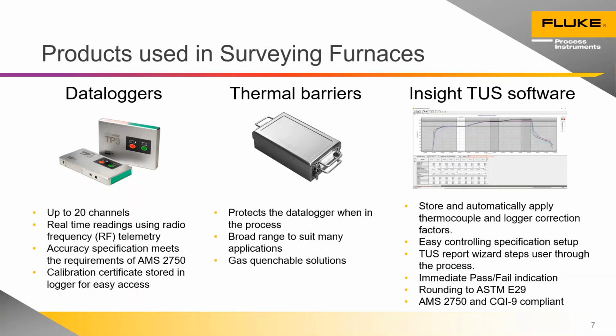Products used in surveying furnaces: data loggers are the heart of the system, measuring the temperature recorded by the thermocouples. They're most often supplied with type K or type N thermocouples, but can also be specified with different types. The image on the left shows a 20-channel unit with 10 type K and 10 type N channels, hence the changing color of the thermocouple sockets — so for surveying different furnaces, you might have different thermocouple requirements, and this allows one data logger to be used across different applications.